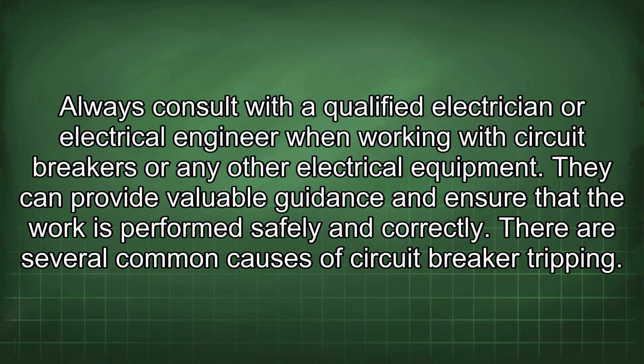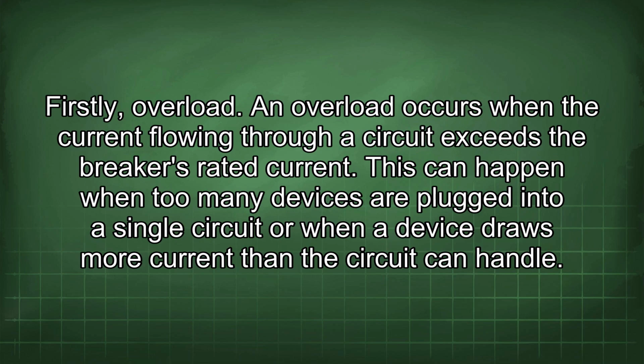There are several common causes of circuit breaker tripping. Firstly, overload. An overload occurs when the current flowing through a circuit exceeds the breaker's rated current. This can happen when too many devices are plugged into a single circuit or when a device draws more current than the circuit can handle.